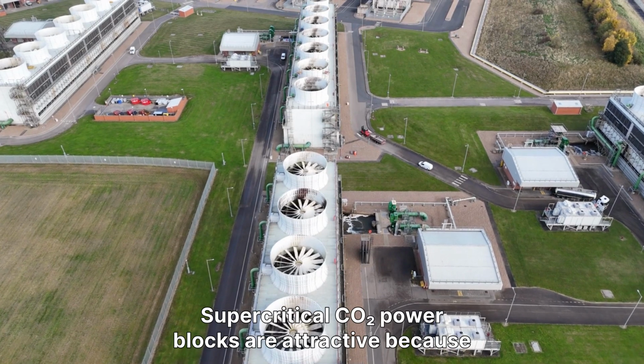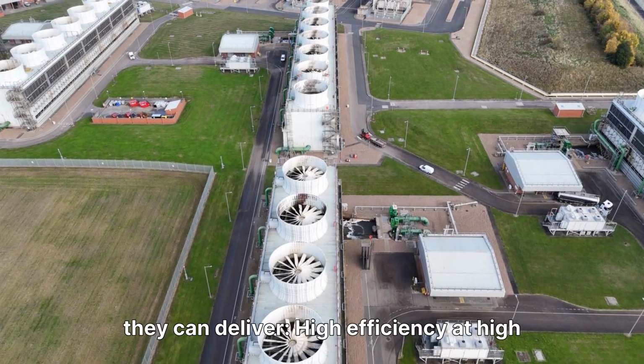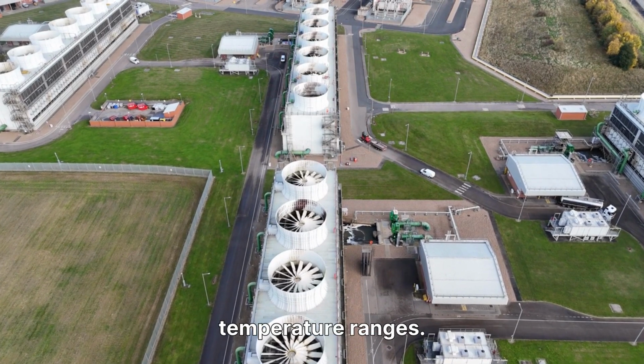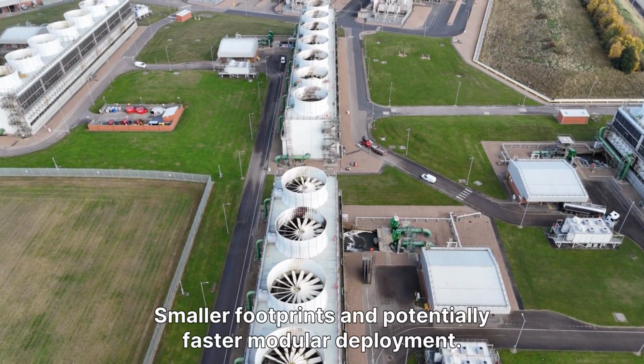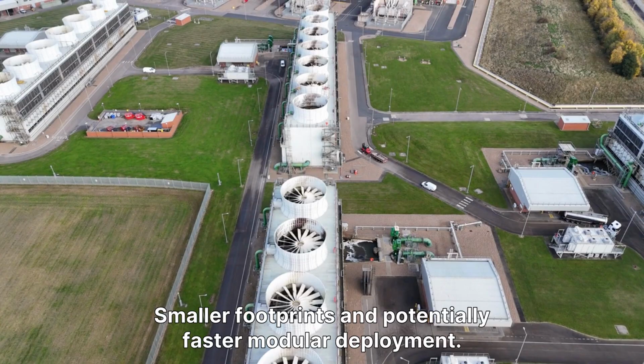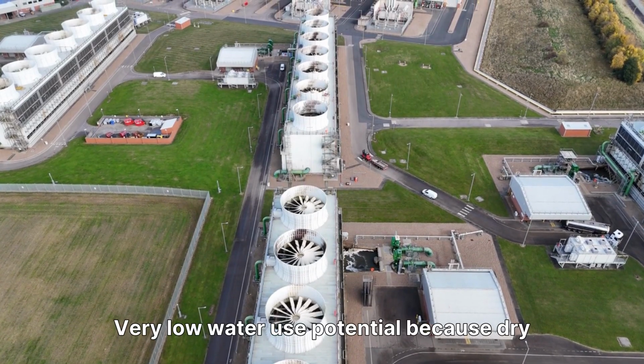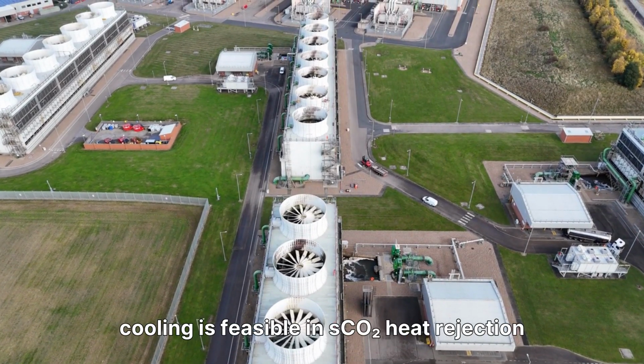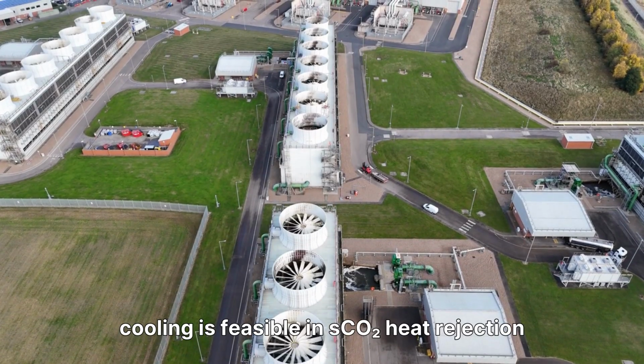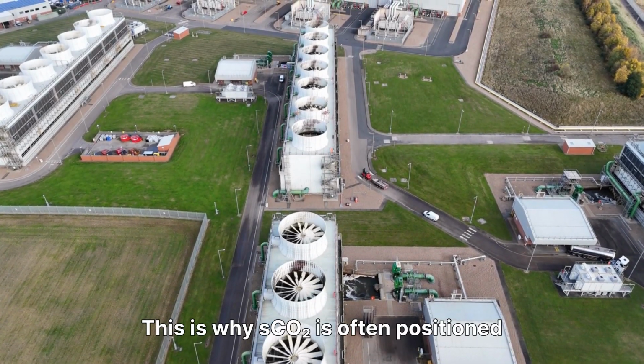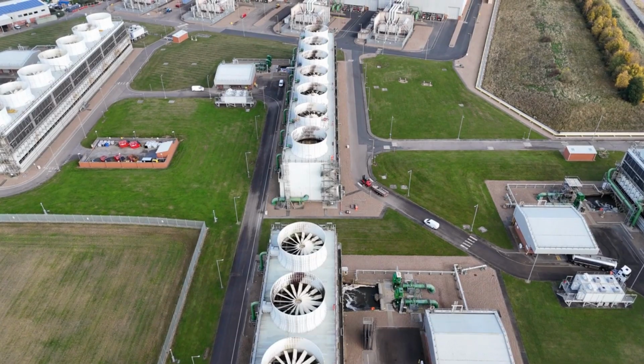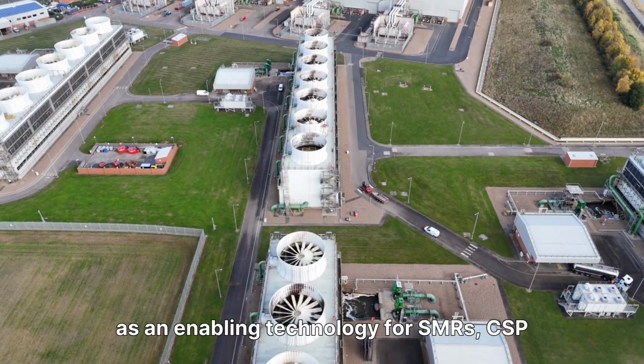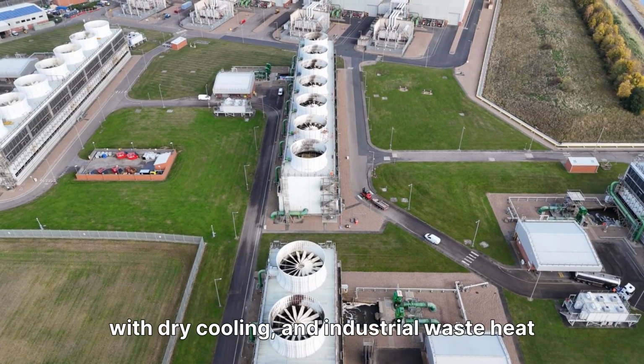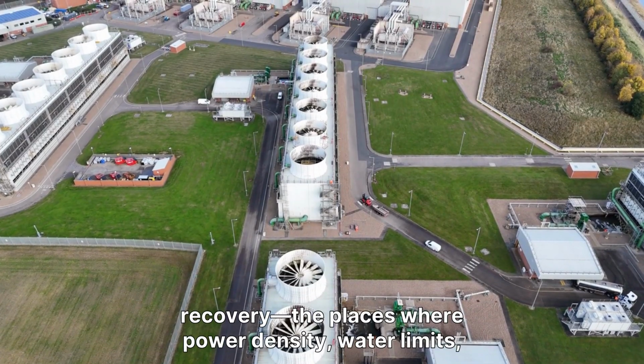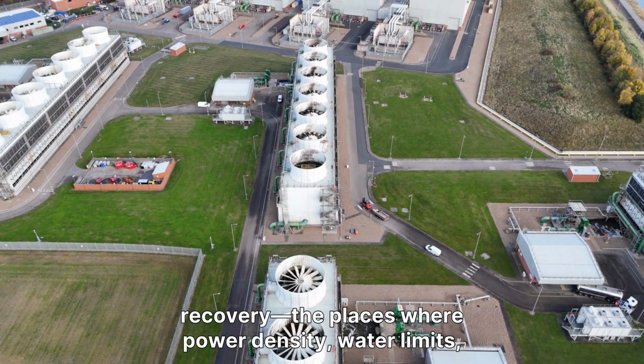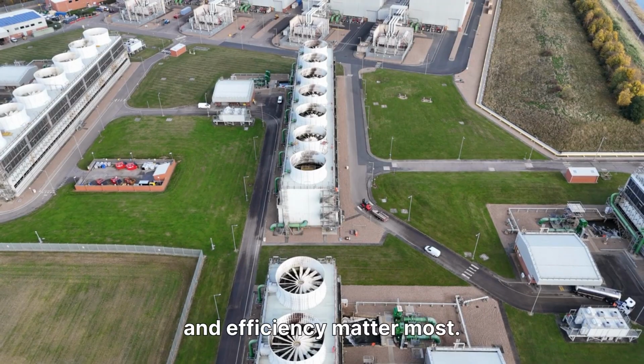Supercritical CO2 power blocks are attractive because they can deliver high efficiency at high temperature ranges, smaller footprints, and potentially faster modular deployment. Very low water use potential because dry cooling is feasible in SCO2 heat rejection designs. This is why SCO2 is often positioned as an enabling technology for SMRs, CSP with dry cooling, and industrial waste heat recovery, the places where power density, water limits, and efficiency matter most.